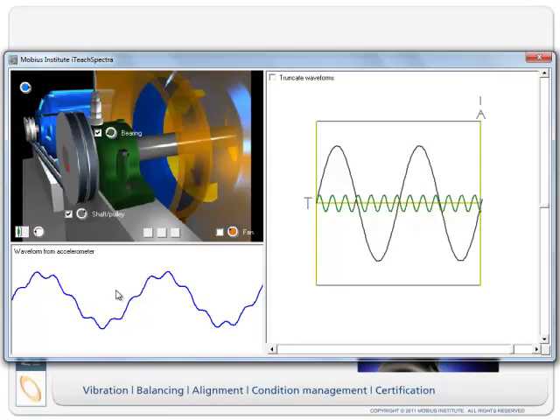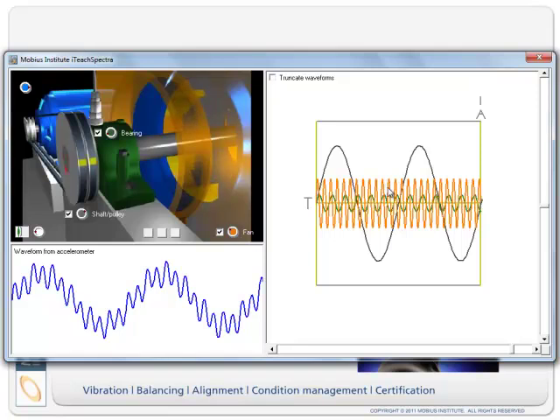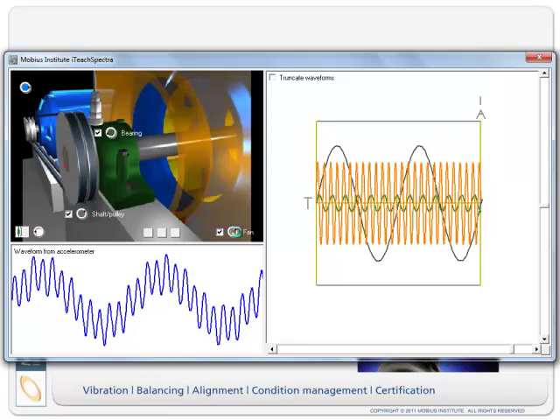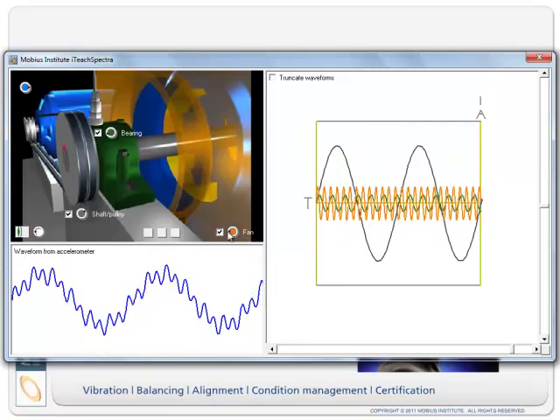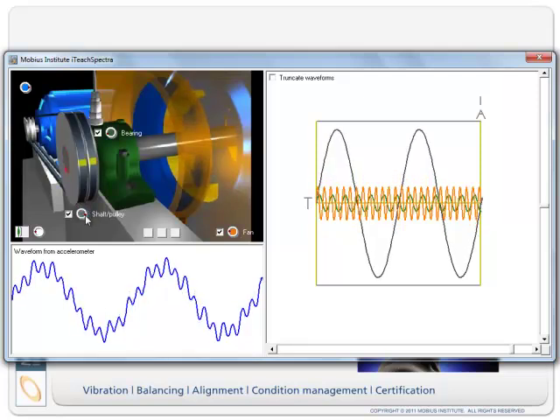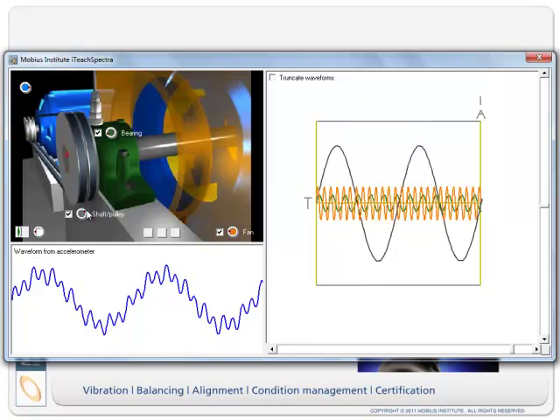In reality, this is the waveform that comes from the sensor. It's a combination of all the sources of vibration which cause this bearing housing to vibrate. The once per revolution vibration, the vibration from within the bearing itself and the vibration from the fan, which I'm showing here is orange because the fan was an orange sort of color. And I can make the fan vibration higher and I can make it down much lower. But here I'm seeing the combination of all three vibrations, depending on how the amplitude of the three are in proportion to each other, determines how this waveform looks down here.